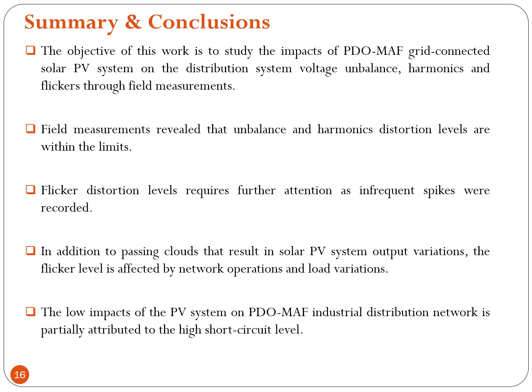The main objective of this work is to study the impacts of the PDO-MAF grid-connected solar PV system on the distribution system voltage unbalance, harmonics, and flicker through field measurements. The field measurements revealed that the unbalance and harmonic distortion levels are within the limits. However, the flicker distortion level requires further attention, as infrequent spikes were recorded, in addition to the passing clouds that result in solar PV system output variation. The flicker level is affected by network operation and load variation.